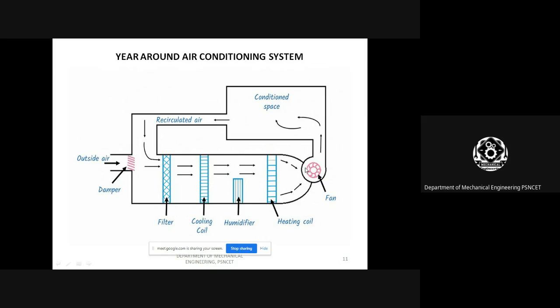And then the fan. For summer air conditioning, the cooling coil is operated, the humidifier is not operated, and the heating coil operates, right? For winter air conditioning, the cooling coil acts as a preheating coil, the humidifier is also working, and this heating coil is also working. This is the year-round air conditioning system. After the heating coil, the air goes to human comfort by means of this duct or fan to the conditioned space, and then is recirculated in the circuit of the year-round air conditioning system.